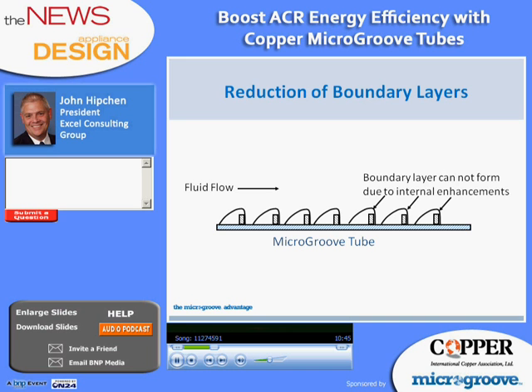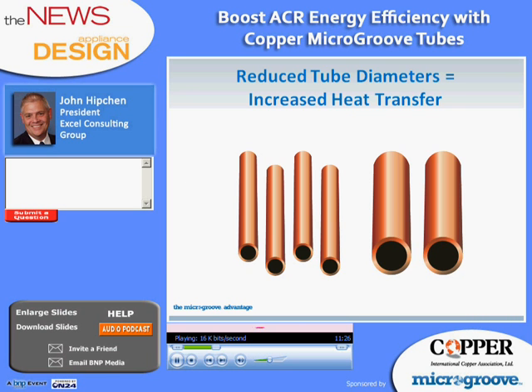In a tube with MicroGroove enhancements, you can see the boundary layer begins to develop, but it breaks down as it moves over the grooves. The additional mixing of the refrigerant that occurs inside the tube because of these grooves increases the amount of refrigerant that comes in contact with the tube wall. The positive effect on heat transfer from these internal enhancements has been known for a long time and applied commercially for over 20 years. And when combined with small diameter tubes, we have even more advantages that we're going to look closer at.